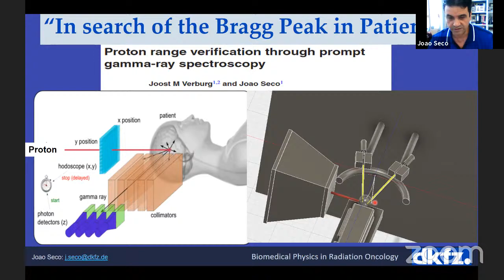Right? You have two images, which is the two yellows, which see the prompt gammas, and you see the Bragg peak. You basically localize it. And so the trick is to have a red beam line, a beam coming in that produces a Bragg peak. You take an image of all the prompt gammas before and after the Bragg peak, and you localize where the Bragg peak is. And this can be done real time, more or less at the millisecond level. So you have real time imaging of the beam. And ultimately, you always want to put the two of them together so that you know where the anatomy and the beam is, so that you have maximum control of the treatment.